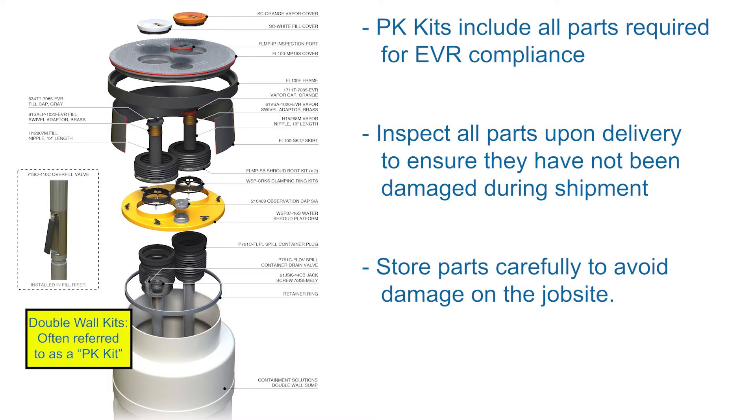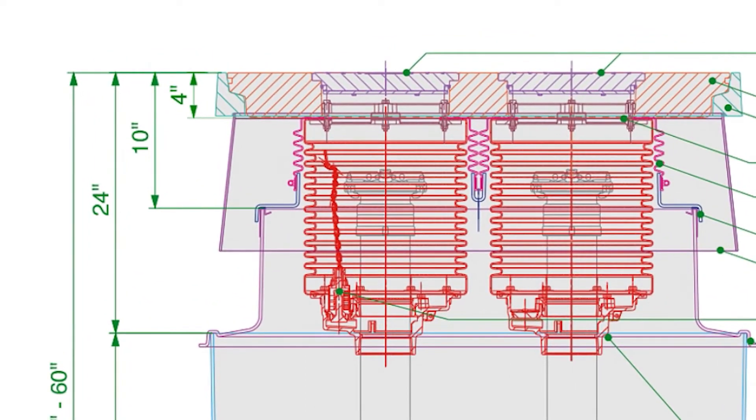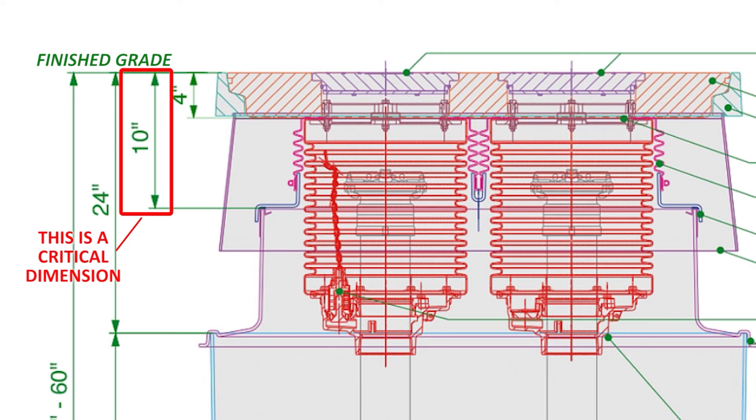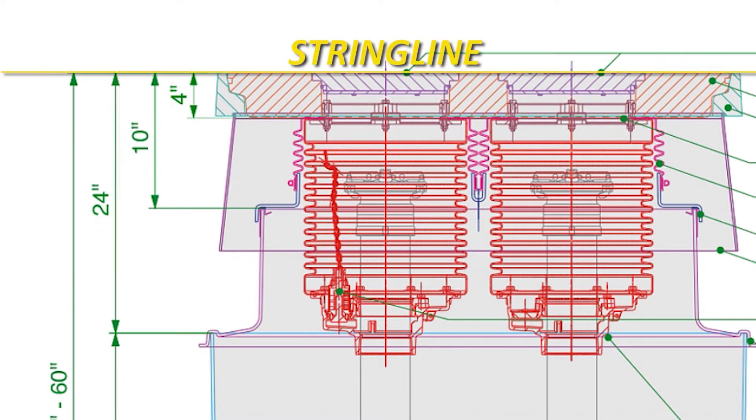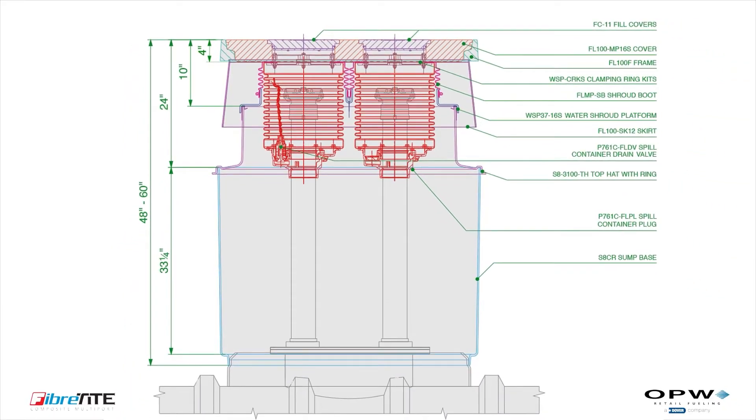The FibreTITE multi-port kit will not work properly unless installed as shown in this dimensional drawing. Regardless of the manufacturer sump base being used, the top of the FibreTITE top hat must be installed 10 to 12 inches from finish grade. Finish grade is defined as the level at which the top of the multi-port frame or cover will be installed, typically 1 to 2 inches above the tank pad level to allow water to drain. Check this dimension by running a string line at finish grade and dry-fitting the top hat. Installing the top hat too low may make it difficult to install the shroud boots; installing it too high may make it difficult to install the multi-port cover into the frame.